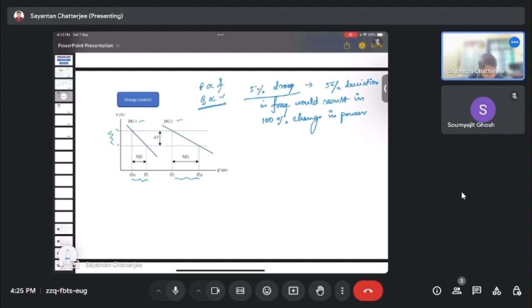These are also cases for the generators. The 5% droop characteristics are also available for synchronous generators, where based on these group characteristics we can say how the dispatch would be delivered and what amount of dispatch would be delivered. Suppose we have a demand of 500 megawatt, how this would be distributed amongst two, three or five generators, based on how fast they respond and maintain that operational behavior within 5%, or rather the x amount of change in the loop.